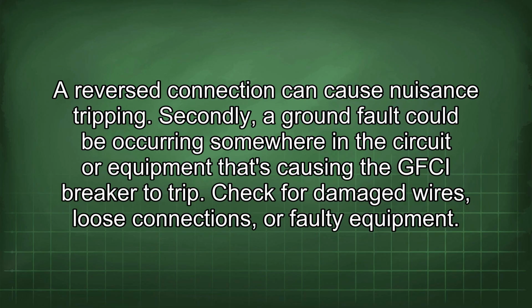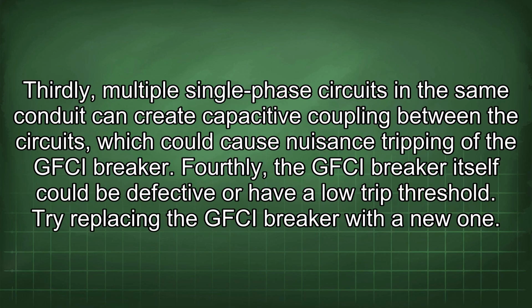Secondly, a ground fault could be occurring somewhere in the circuit or equipment that's causing the GFCI breaker to trip. Check for damaged wires, loose connections, or faulty equipment. Thirdly, multiple single-phase circuits in the same conduit can create capacitive coupling between the circuits, which could cause nuisance tripping of the GFCI breaker. Fourthly, the GFCI breaker itself could be defective or have a low trip threshold. Try replacing the GFCI breaker with a new one.